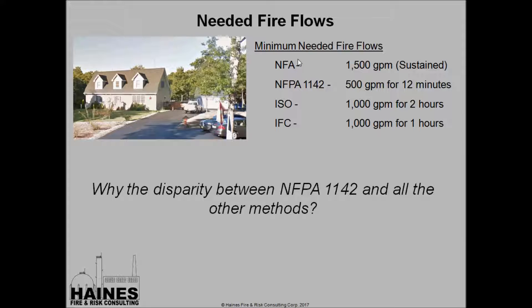Summarizing the needed fire flow recommendations: 1,500 GPM under the National Fire Academy; 500 GPM for 12 minutes under NFPA 1142; 1,000 GPM for two hours under ISO; and 1,000 GPM for one hour under the IFC. I don't understand why there's such a disparity between NFPA 1142 and all the other methods — we'll discuss this in the next slides.